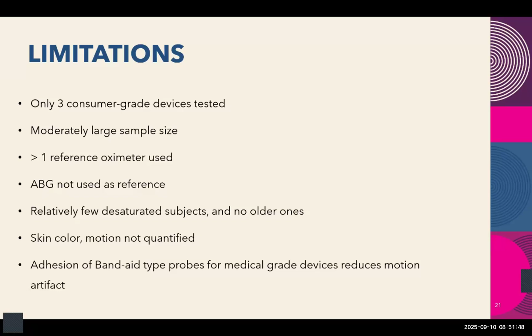And for little kids, we of course use the Band-Aid probe that all of you are used to, and that's not really a fair comparison because for a squirmy little 2-year-old, a Band-Aid probe is going to get more accurate readings than any of these fingertip devices will. So, in terms of what it all boils down to, first of all, pulse oximeters have more trouble with little kids because their fingers are smaller. There's less blood in there, there's less signal to work with. And that's going to be true of any pulse oximeter. In addition, kids move around, and oximeters have trouble with that.